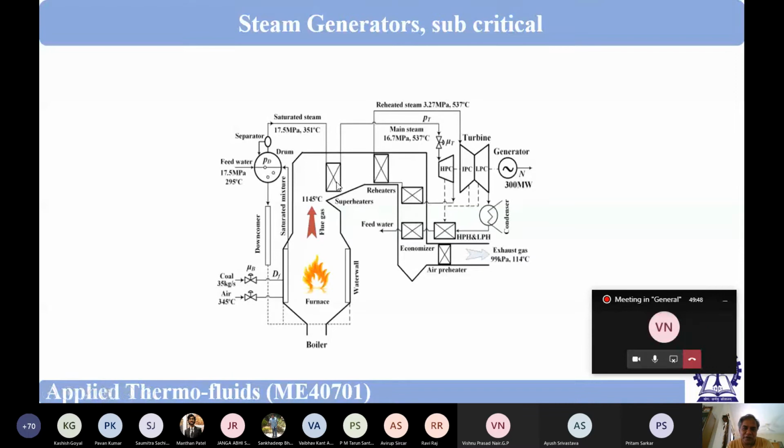So this is showing the superheater. Okay, superheaters, it is written because there are a number of superheaters. Two, three superheaters will be there. Means not the same design, but two, three different types of superheaters will be there. Okay, this is very important that only saturated steam should go to the superheater, no liquid droplet. So that's why separation is important. I will elaborate this later on also.